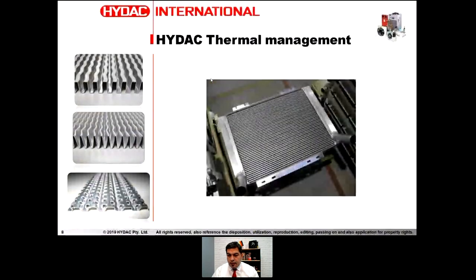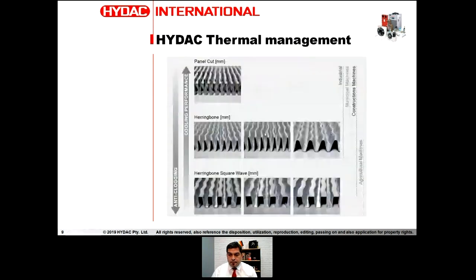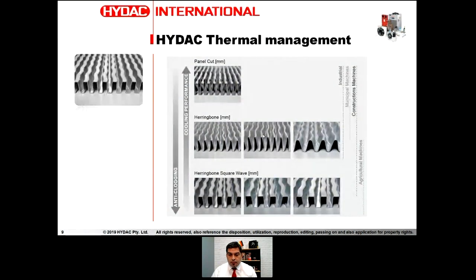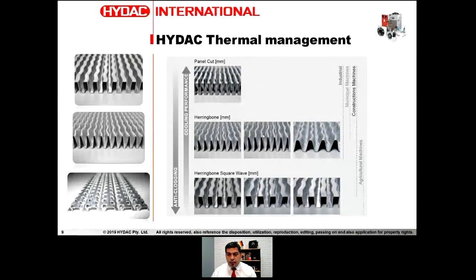HYDAC uses what we call a cooling element: a cooling core in the middle with two tanks on the side. The middle part is composed of fins — air fins externally and turbulators internally. We have a lot of variety at HYDAC; it's our biggest point of differentiation. The tighter the air-side fins, the more performance is enhanced; the more open, the less performance — and the choice depends on the sector, whether industrial, municipal vehicle, or construction equipment.